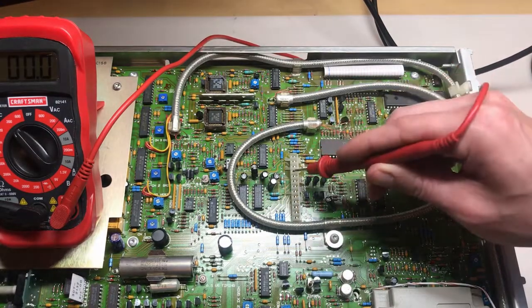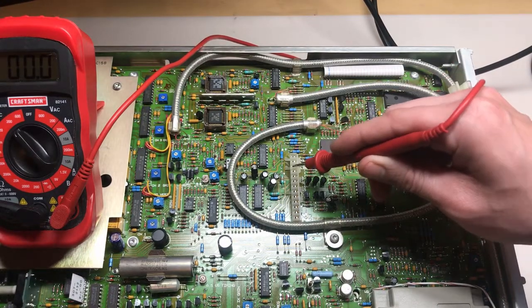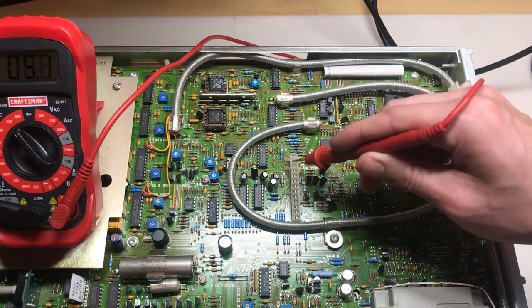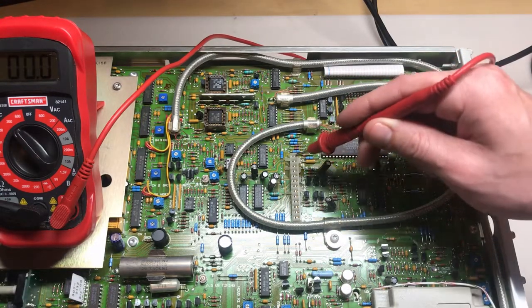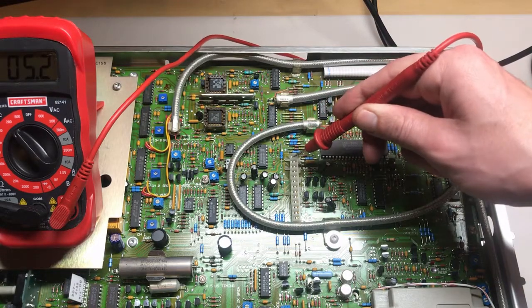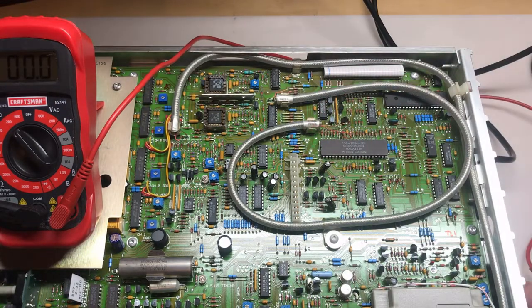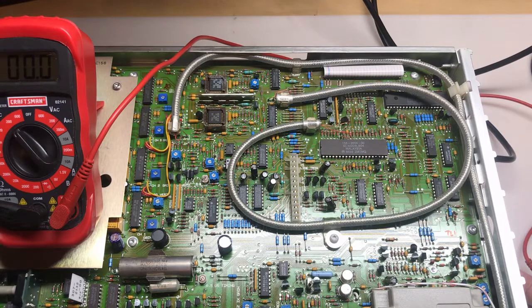Next one should be ground, so that shouldn't show anything. Next one is line trigger. Here's positive 5, yep, and then the last one should be positive 5. Okay, so the only real area of concern as far as voltages go is that the minus 15 is missing. So pull up the schematic and again see if that is at all involved in the horizontal deflection circuitry. And we'll have to pull the power supply out and try and identify where the minus 15 is getting pulled down or just not being generated.